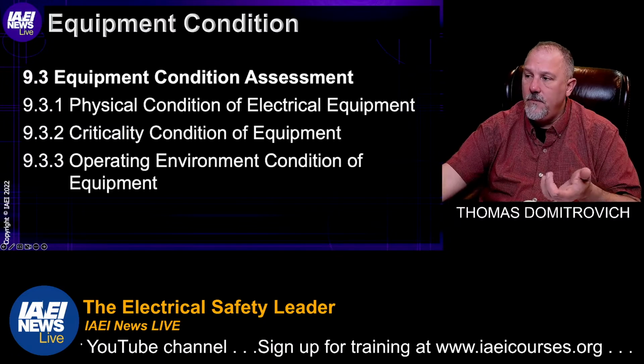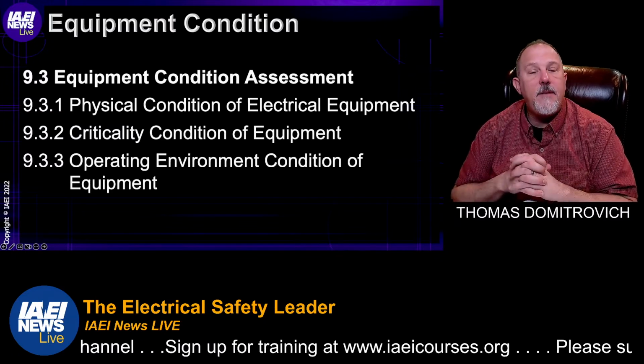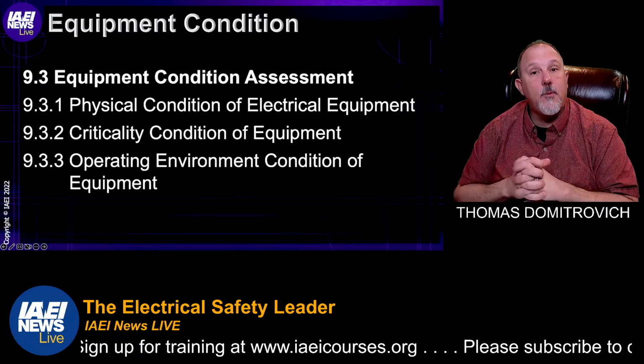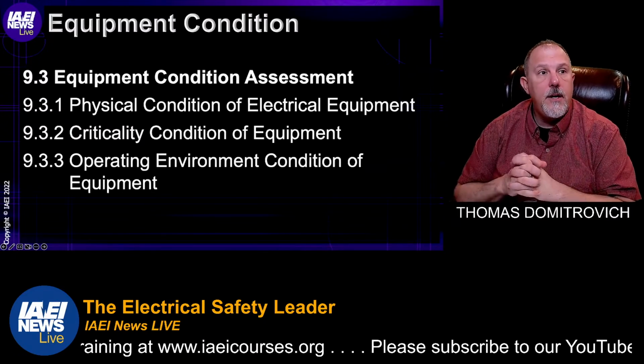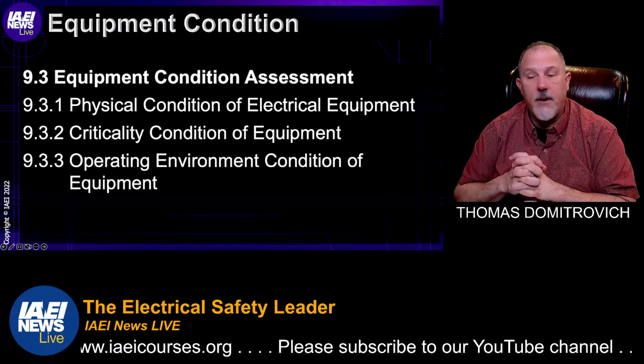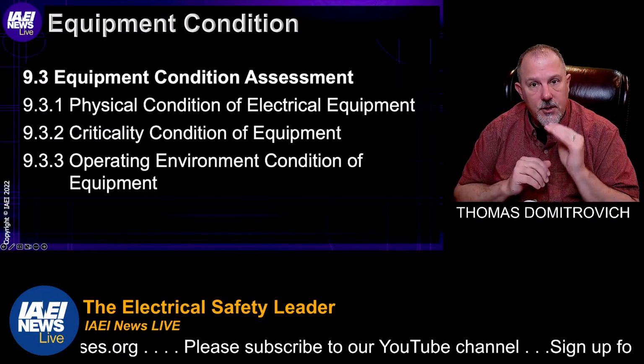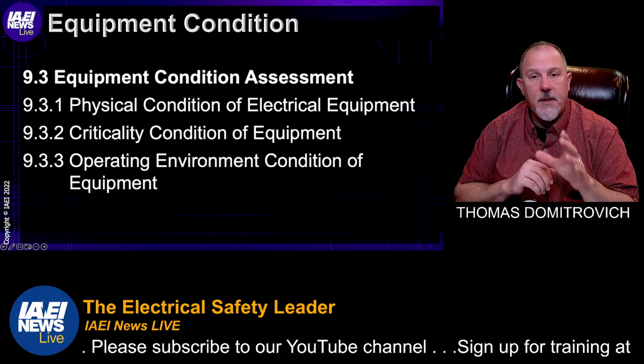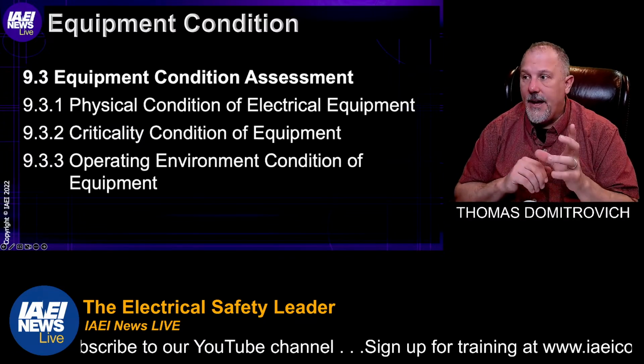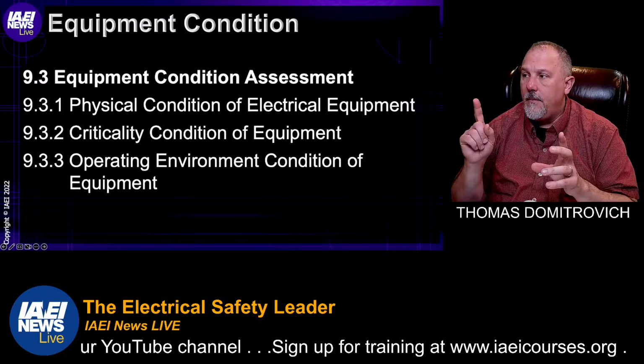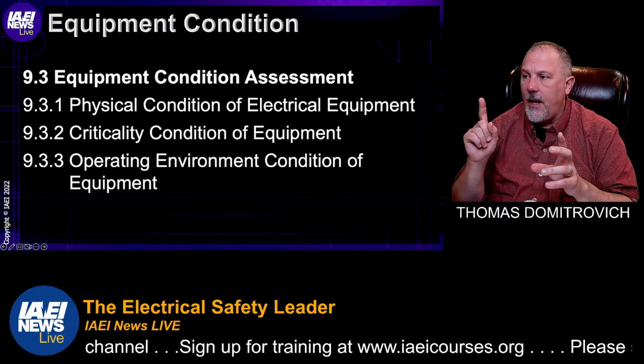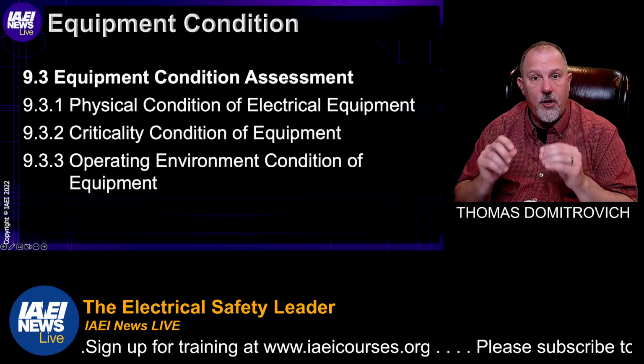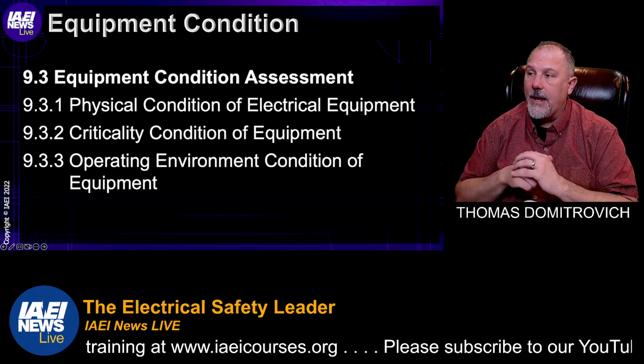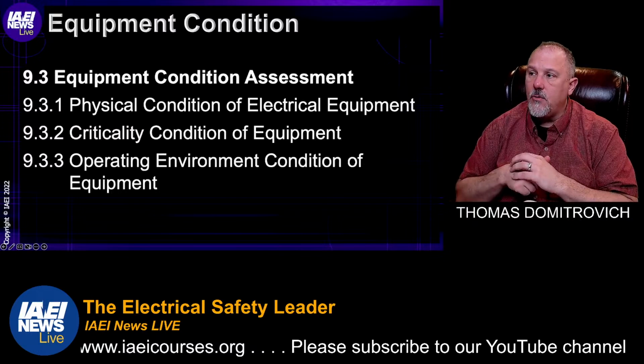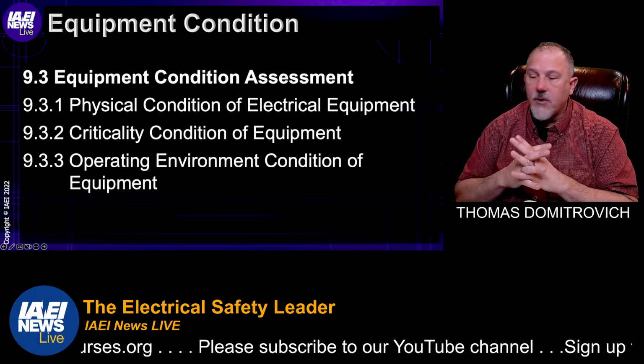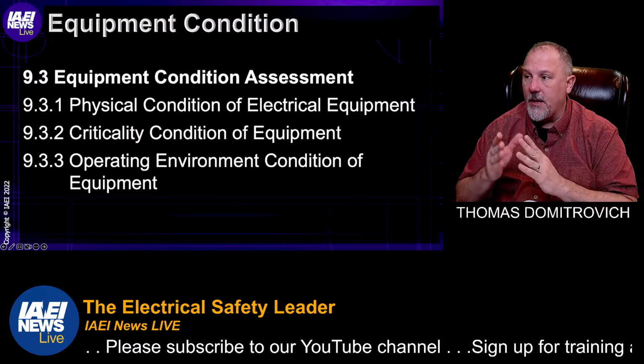Physical condition 2 is if I had maintenance. So, for example, maybe I had to replace a circuit breaker because it saw a very high fault current, interrupted a very high fault current. I may have to replace a circuit breaker or a fusible switch or something of that nature inside that equipment. Those are more frequent maintenance than what you might plan on having for that equipment. So equipment physical condition 2 is the previous maintenance cycle has revealed issues requiring the repair or replacement of major equipment components.